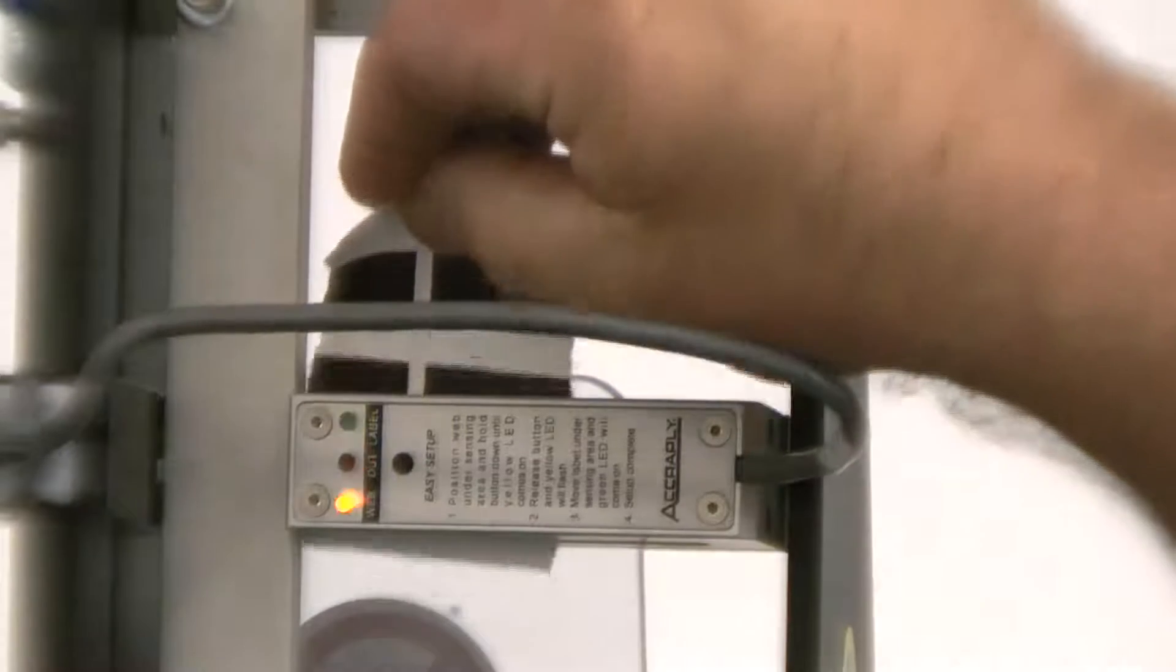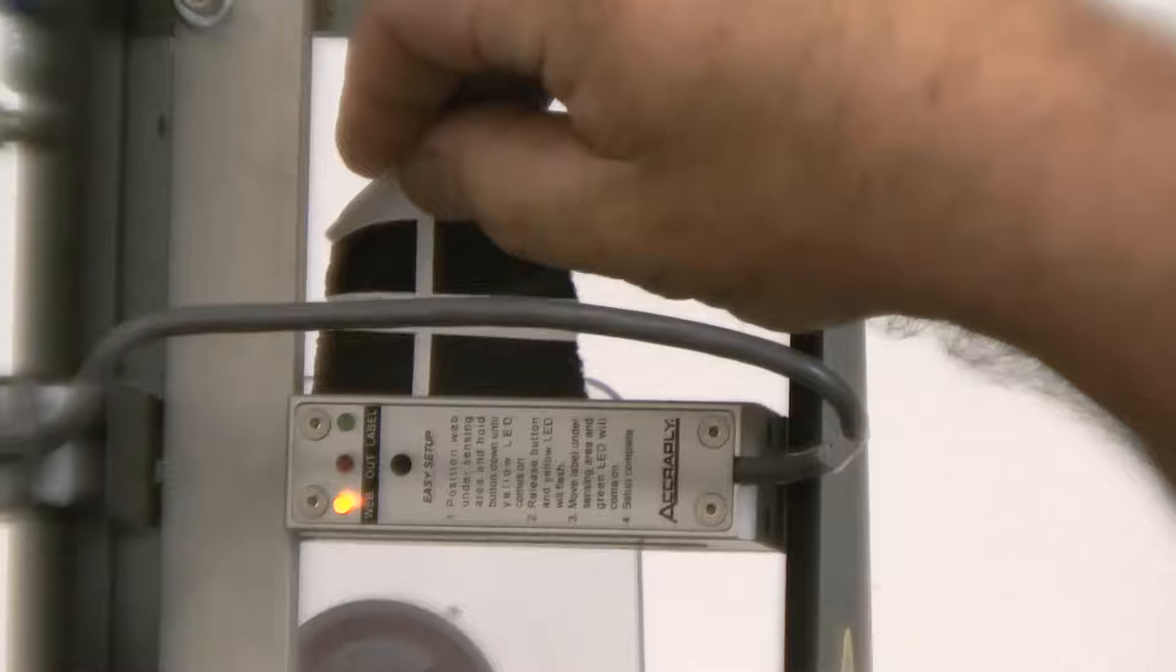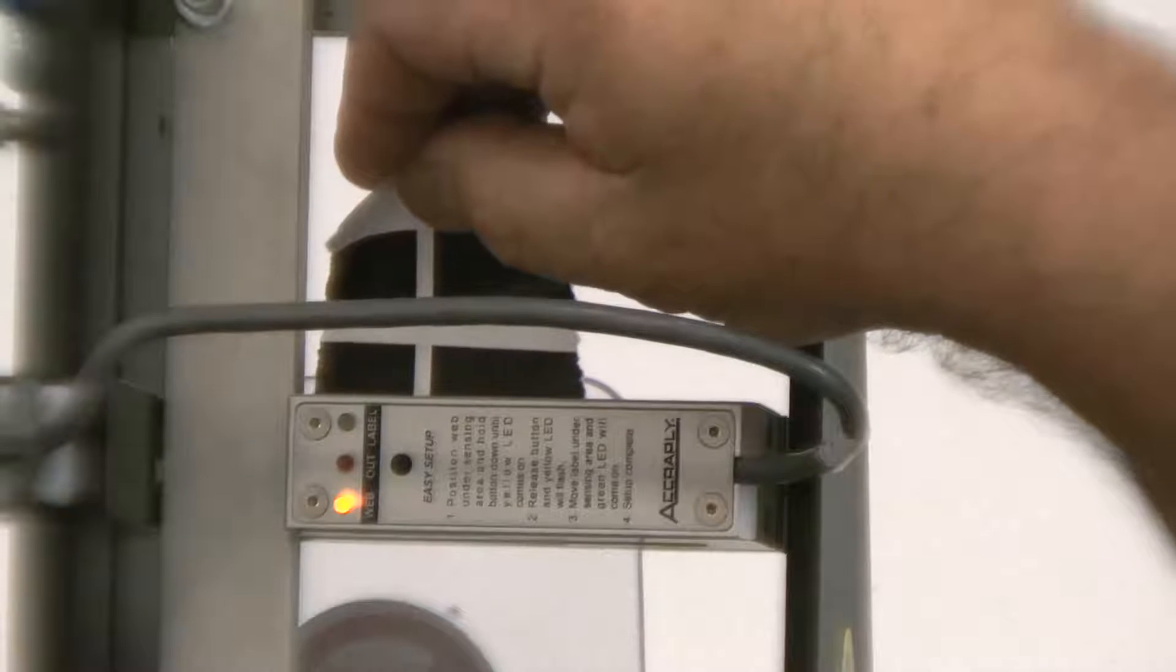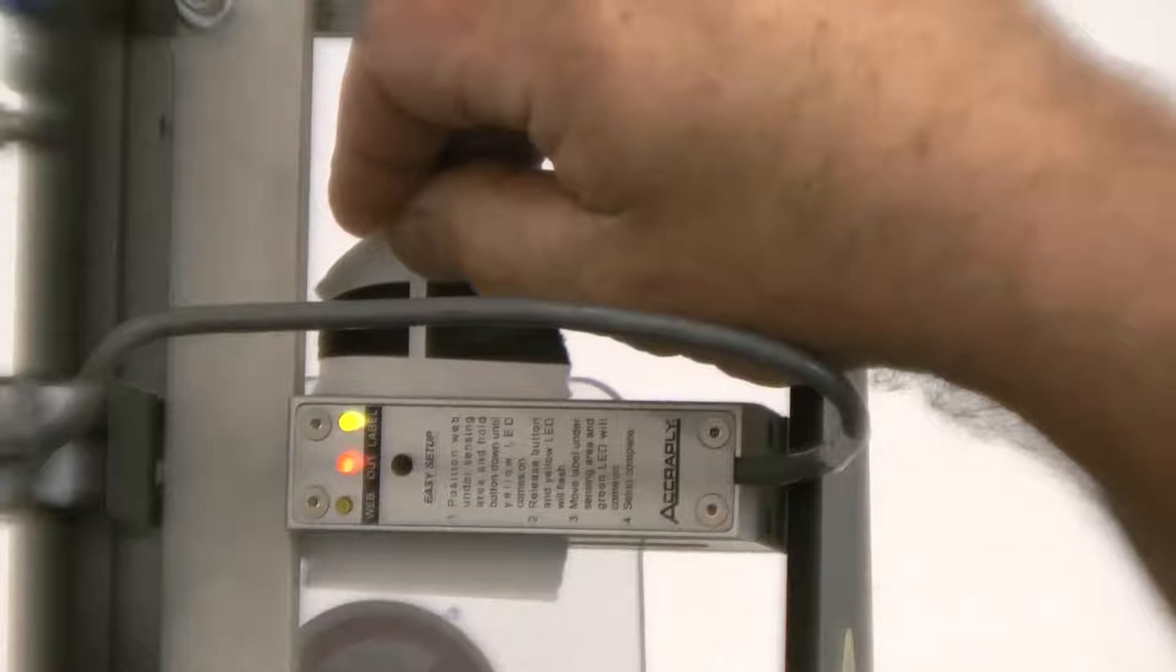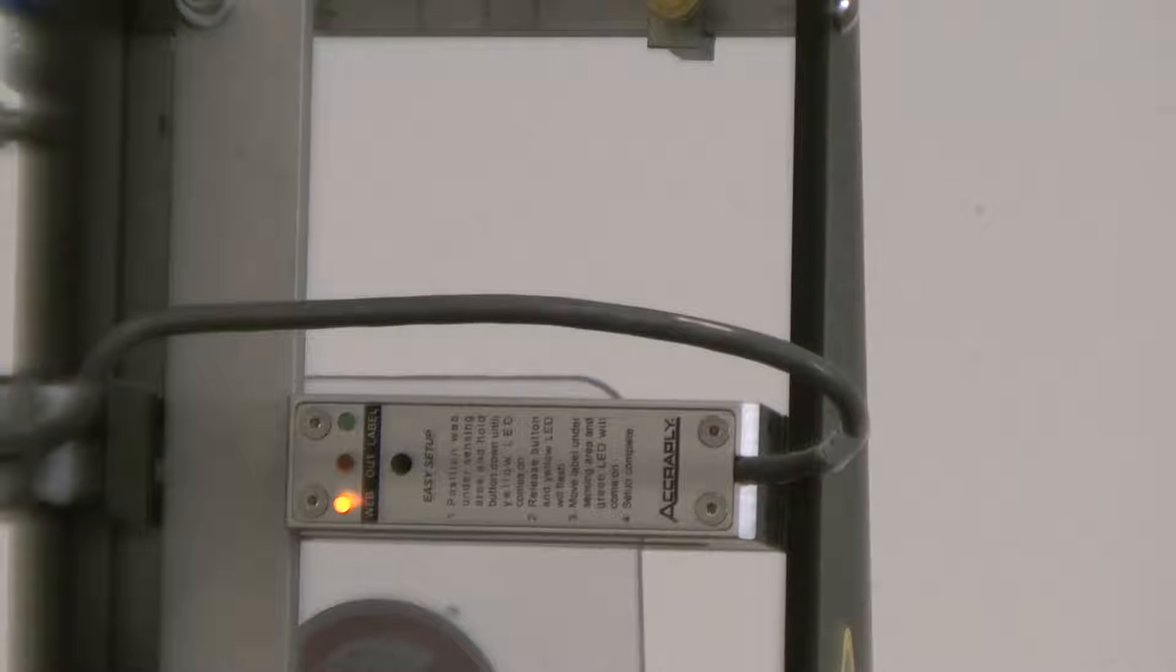By moving the web in and out of the sensor, you can see that when the white is in the sensor, the yellow light is on. When the black is in there, the green and red comes on. At this point, the sensor is properly trained and you can thread the labeler and begin running.